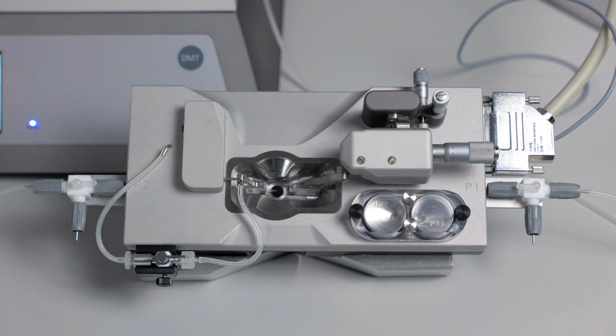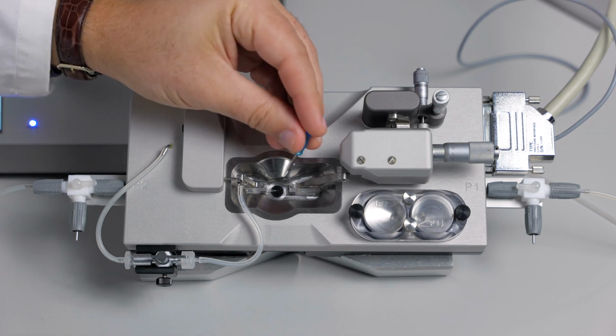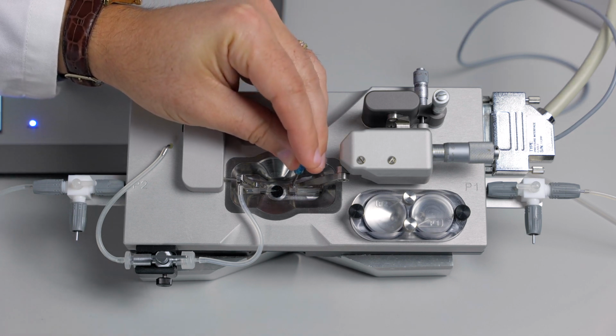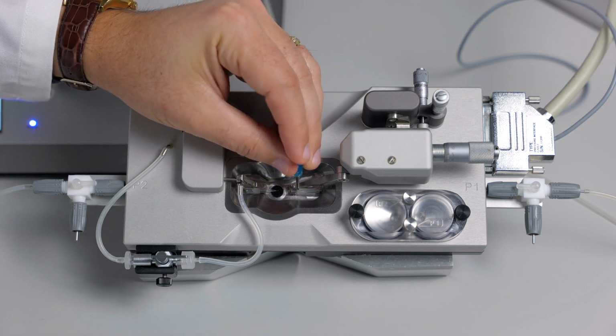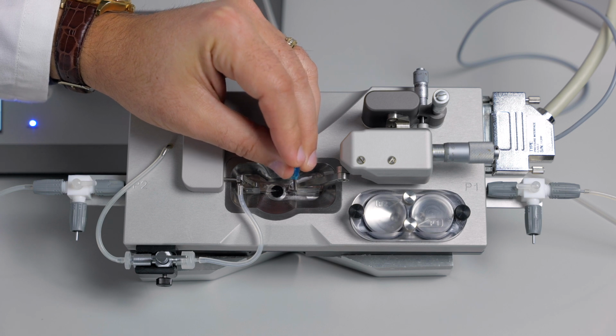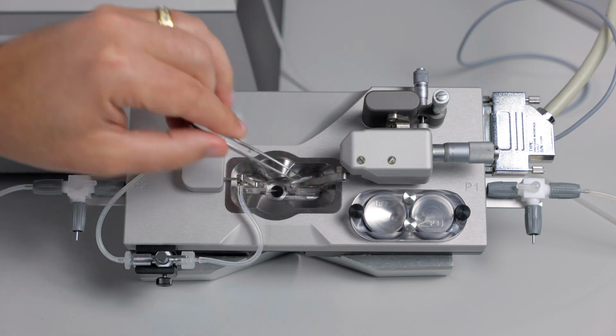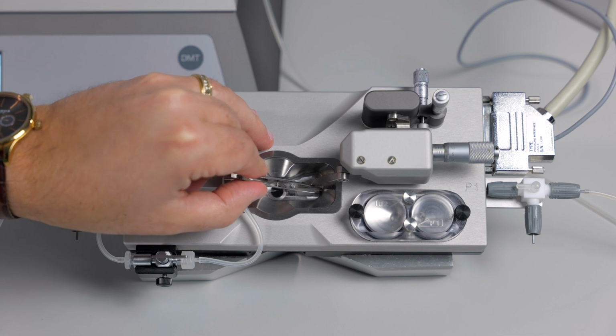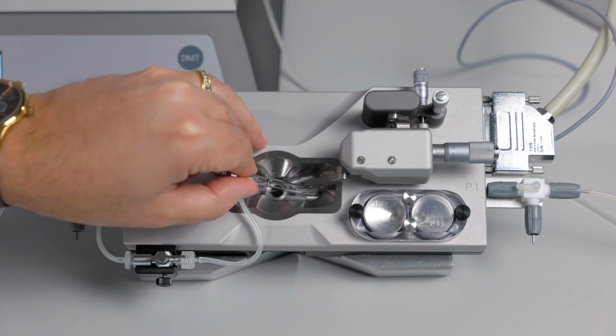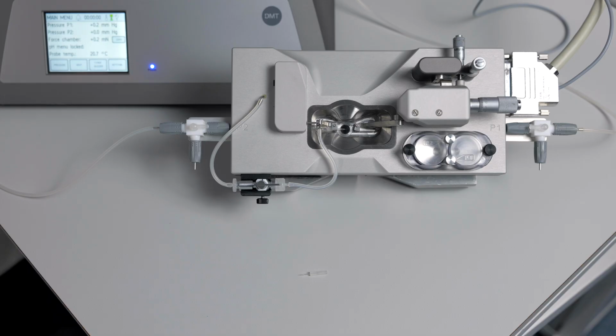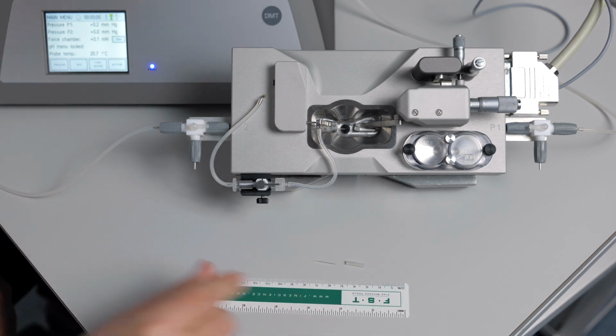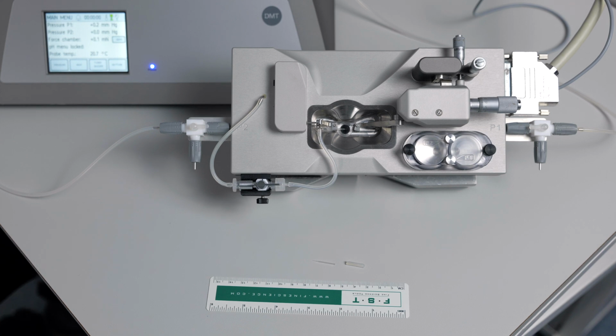If you need to replace the right side or P1 cannula, you will simply loosen the plate that holds it in place. You can swing that out of the way and pull the tubing off of the port. After you've removed the P1 tubing and cannula, you will need to separate them so you can replace both parts. You will need to use a ruler so you can match the lengths when replacing these parts.